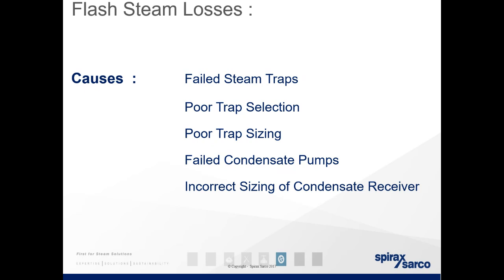So if that's mechanical or electrical, it's not able to clear the condensate from the steam system. Again, you will see the challenges of flash off there, loss of energy there, more condensate in your system, and incorrect sizing of condensate receivers. So if you have a receiver which is undersized and is constantly draining water through the overflow to drain, you're seeing a loss there, and because of the pressure differential there, you'll see flash steam too.